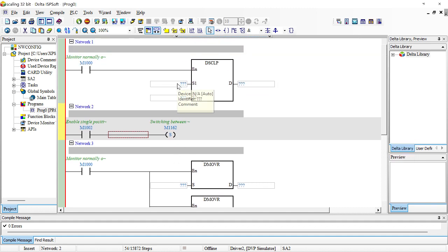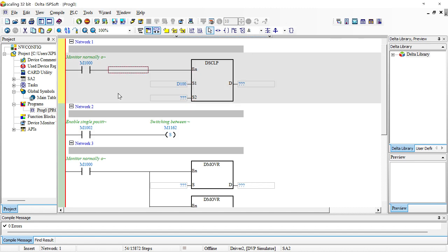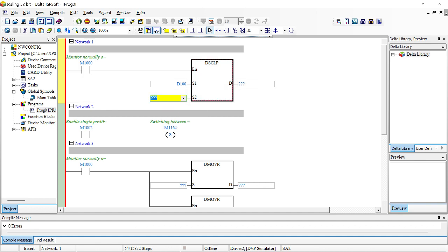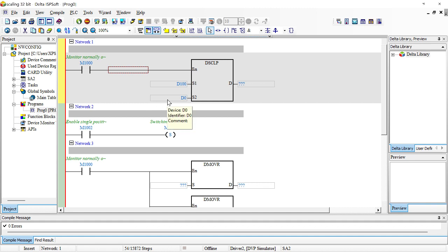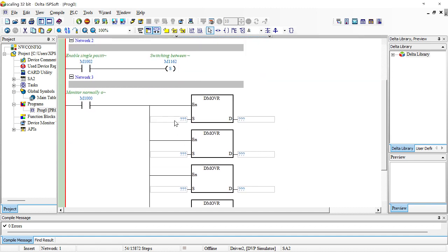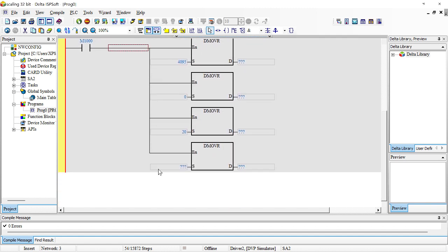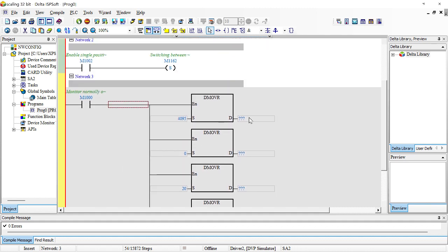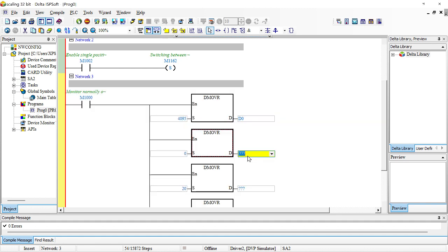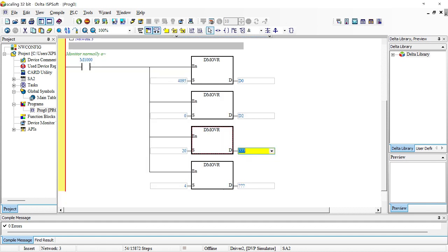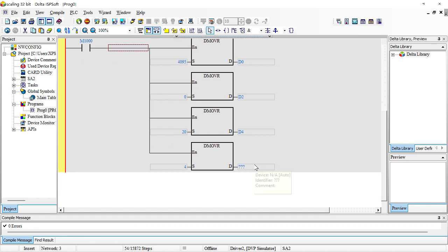My source is coming in as D100. My parameters are starting from D0. Since this instruction uses a double word, it automatically takes D0 and D1. So my source maximum is 4095 and source minimum is 0. Then 20 is the destination maximum and the destination minimum is assigned. D0 and D1 are already taken. The next register is D2 and D3, then D4 and D5, and then D6 and D7.